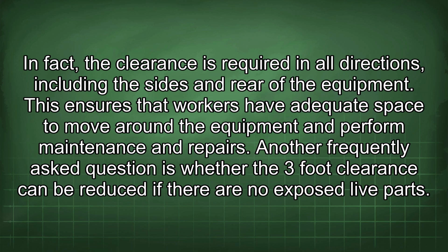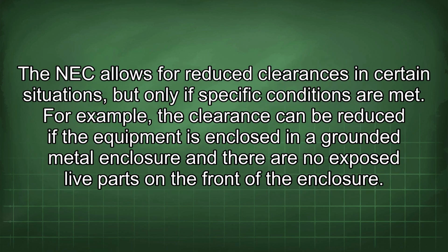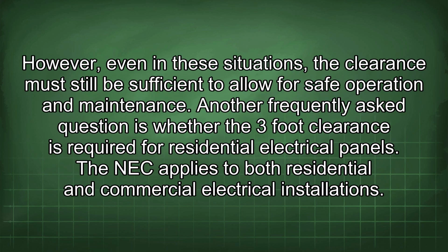Another frequently asked question is whether the 3-foot clearance can be reduced if there are no exposed live parts. The NEC allows for reduced clearances in certain situations, but only if specific conditions are met. For example, the clearance can be reduced if the equipment is enclosed in a grounded metal enclosure and there are no exposed live parts on the front of the enclosure. However, even in these situations, the clearance must still be sufficient to allow for safe operation and maintenance.